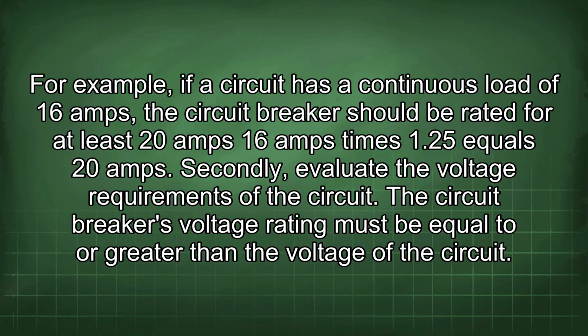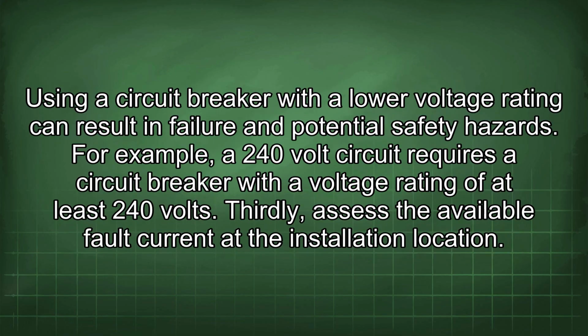Secondly, evaluate the voltage requirements of the circuit. The circuit breaker's voltage rating must be equal to or greater than the voltage of the circuit. Using a circuit breaker with a low voltage rating can result in failure and potential safety hazards. For example, a 240-volt circuit requires a circuit breaker with a voltage rating of at least 240 volts.